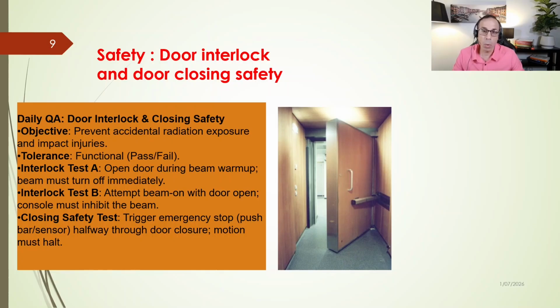These massive vault doors can weigh up to 15 tons to block the radiation, and the motors close them with incredible force. To make sure that the built-in safety features are working, activate the emergency push bar or proximity sensor while the door is halfway through its closing cycle. The door must stop moving instantly. Making sure these safety loops function perfectly every morning is your first and most important task before any patient steps into the room.